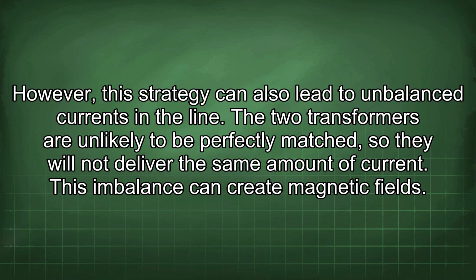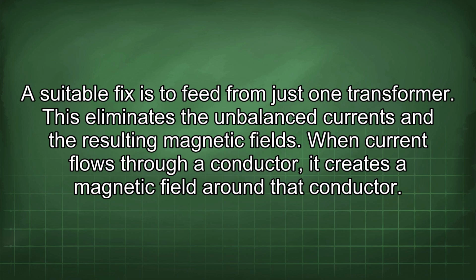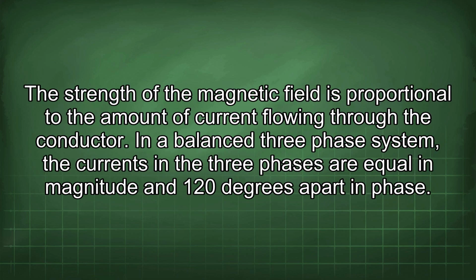The two transformers are unlikely to be perfectly matched, so they will not deliver the same amount of current. This imbalance can create magnetic fields. A suitable fix is to feed from just one transformer. This eliminates the unbalanced currents and the resulting magnetic fields. When current flows through a conductor, it creates a magnetic field around that conductor. The strength of the magnetic field is proportional to the amount of current flowing through the conductor.